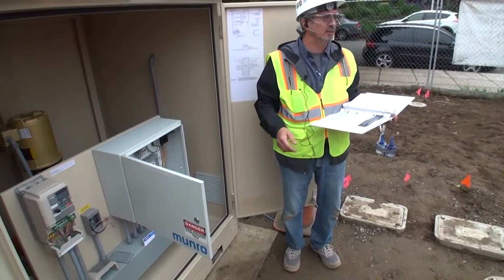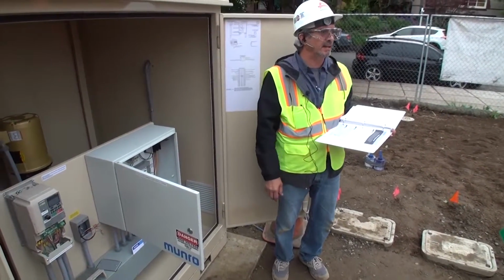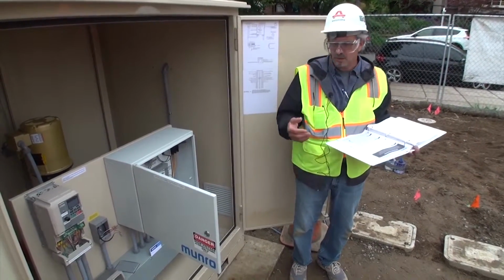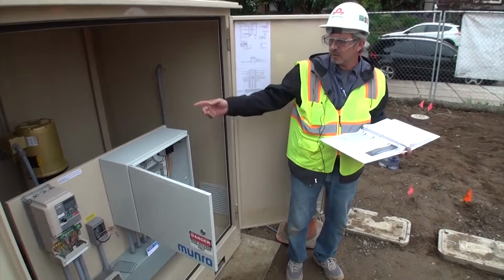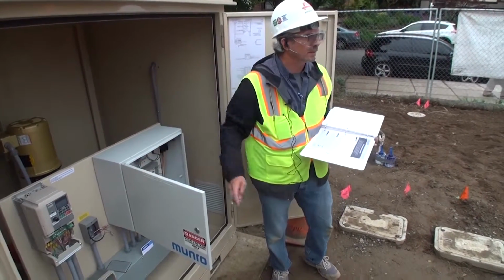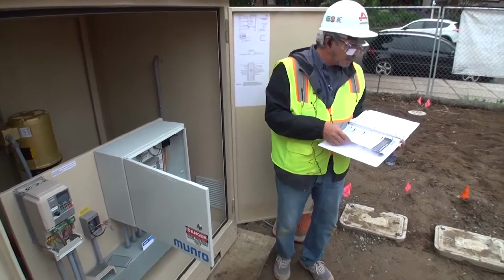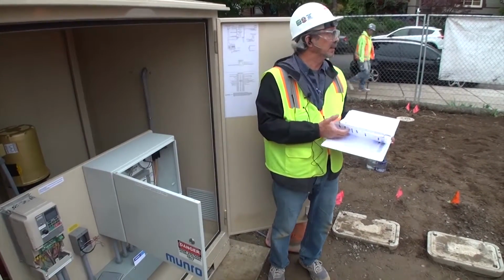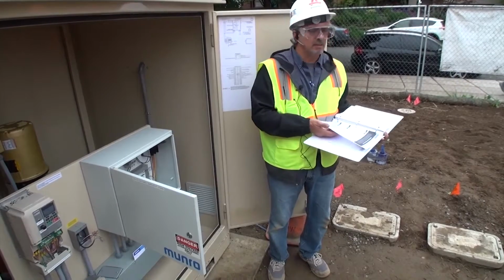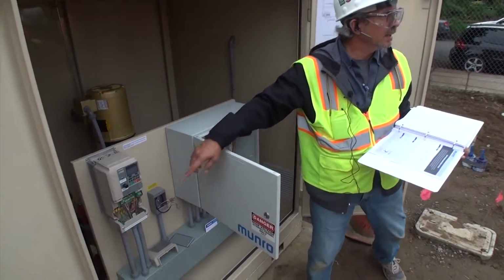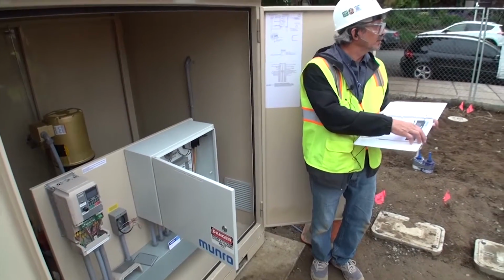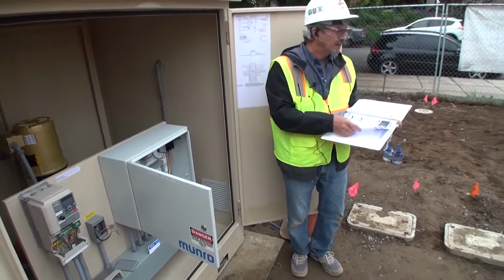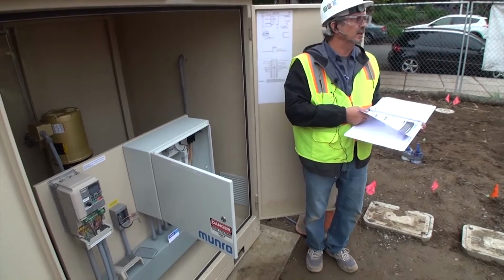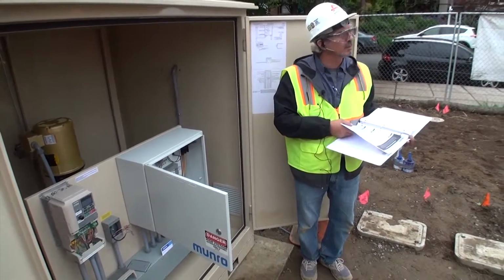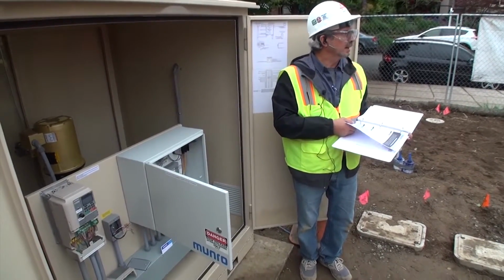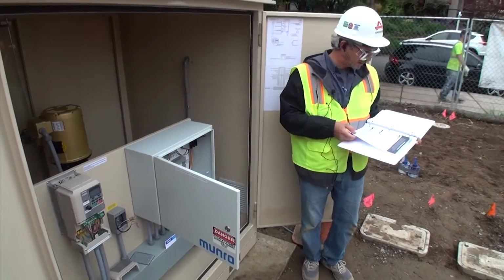You're going to want to measure your amperage loaded, so put as much of a load on it as you can and then measure your amperage. If you're doing across-the-line pumps, you would do it on individual lines. If you have a drive, it will tell you the amperage on the display. As for the Megger readings, I don't imagine you're going to have a Megger, which is an insulation tester. You would put it on the output wires, and you would not want to run 1,000 volts on this while it's hooked up, so you'd disconnect it first. You probably won't bother with that out here. The drive has its own insulation test measurement, and you don't really require that in this application.